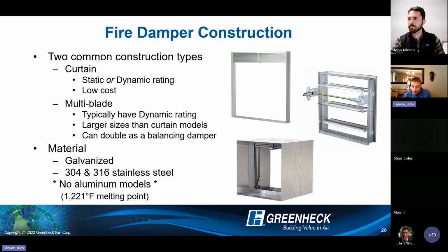I pretty much covered this already, curtain style products. So one thing we will talk about coming up here is the ratings of the products being static or dynamic, essentially meaning if they're tested to close against airflow or not. Static rated products are okay to be used in systems that are going to either automatically shut down in the event of a fire or do not have any significant airflow, like an air transfer opening, something.